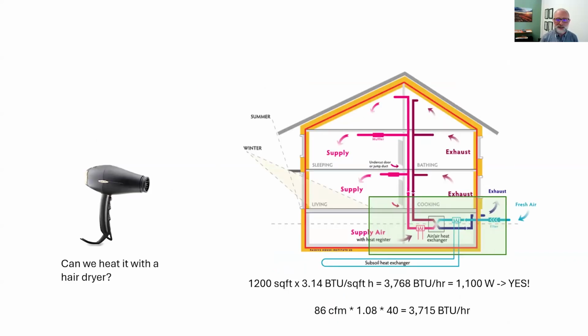The architects of the Passive House system decided that it still made sense to provide some heat to the building in order to allow occupants to control the temperature of their environment. There are several ways to do this, but an elegant approach is to put a bit of heat into the ventilation air, which is already distributed around the structure to provide ventilation where it's needed. In the example case above, we would need approximately 86 CFM of ventilation air to provide the required heat for the building, which is a reasonable amount of ventilation air for a 1,200 square foot house, depending on how many bedrooms and bathrooms you have and the required kitchen exhaust.